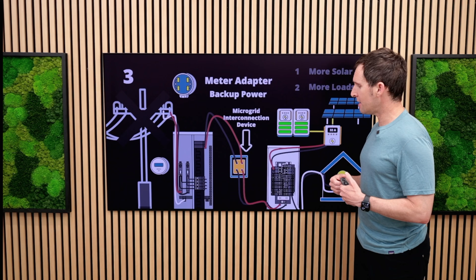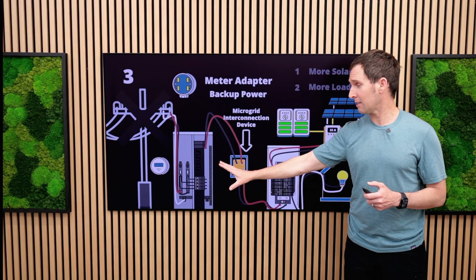The way backup systems have historically been installed is with a central switch that can open. This is kind of like an automatic transfer switch, though it's actually more accurately referred to as a microgrid interconnection device. This opening in the switch is a way so that when the grid is down, this microgrid, with its solar, inverter, batteries, and the loads of a home, is electrically separate from the grid. So the grid can have a blackout and the system will still operate because this switch is open, the connection is open. You can see that opening here in my diagram.